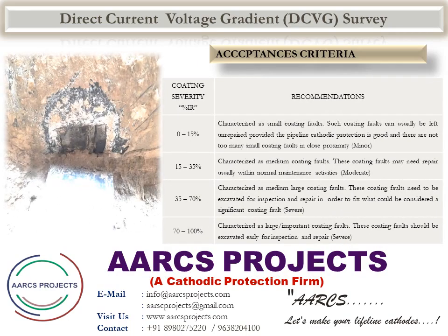Acceptance Criteria: The acceptance criteria of Direct Current Voltage Gradient Survey depend upon coating severity as a percentage IR. 0% to 15% is characterized as small coating faults — minor. Such coating faults can usually be left unrepaired provided the pipeline cathodic protection is good and there are not too many small coating faults in close proximity. Greater than 15% to 35% is characterized as medium coating faults — moderate. These coating faults may need repair, usually within normal maintenance activities.